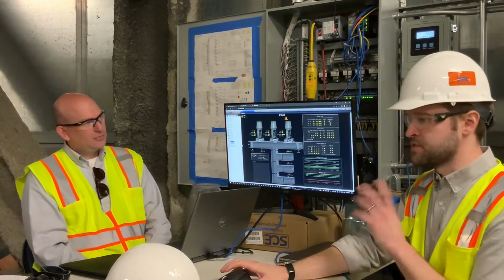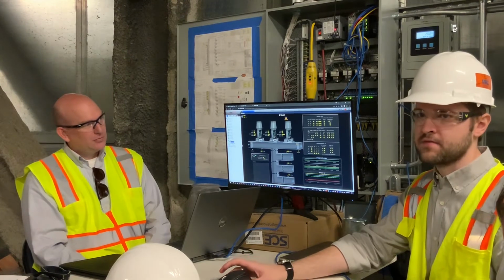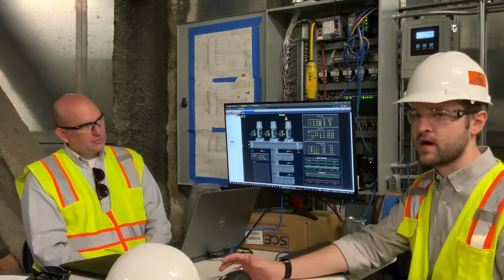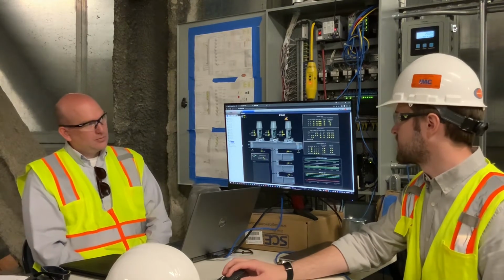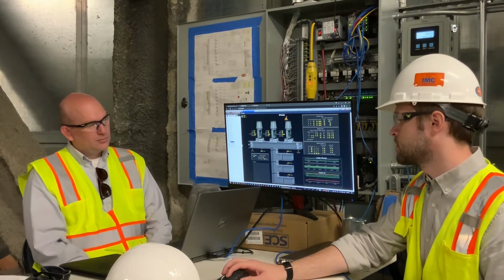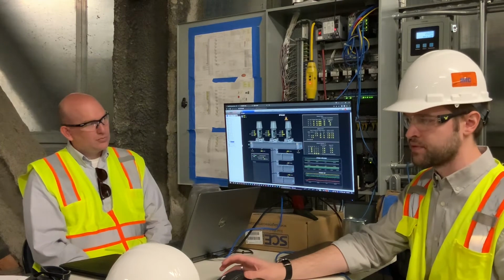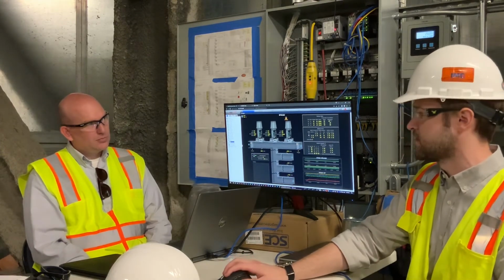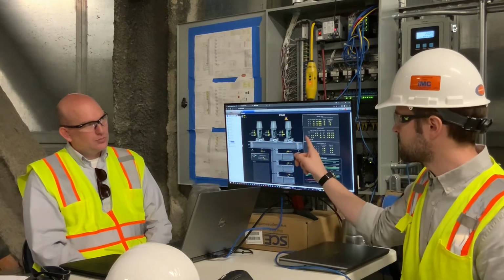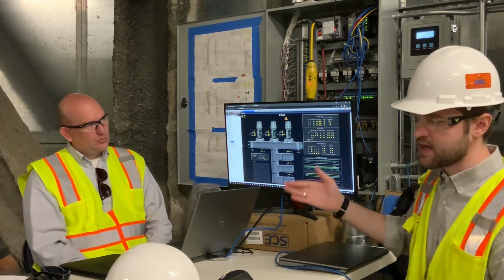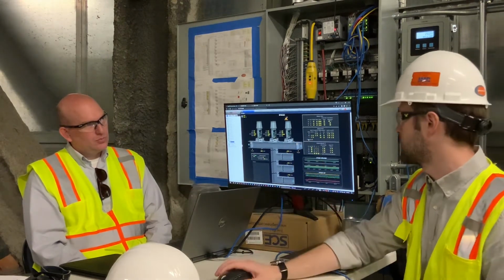This next table here determines the staging of each fan. We spent a lot of time tuning this. I don't anticipate you guys will have to mess with the actual staging parameters of the fans unless something's not working correctly. This really just looks at the parameters that have to be in place to bring on another stage, and it also tells you how many stages are currently active. Over here on the left, normally these numbers will be gray. If that stage is active, the number turns white to tell you that it's active.